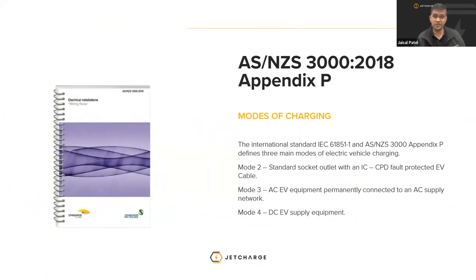Essentially, we need to go over a few definitions of what is detailed in AS3000 Appendix P in terms of what types of charging there are. There are three modes of charging defined under AS3000: mode 2, mode 3, and mode 4. Mode 2 is a standard socket outlet with an in-cord control and protective device, a fault-protected EV cable. So there's an inline cord protection device within the charging cable, which provides control and protection for that circuit. Mode 3 is a permanently connected AC charger, and mode 4 is typically for DC EV supply equipment. So next slide, please.